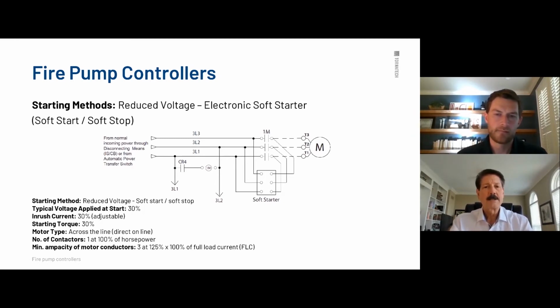So a soft start will allow you to do two things. You could ramp that speed up a little quicker if you want, or you could, it's field adjustable, but it's factory set for the optimum ramp up time for that particular horsepower size motor. You could ramp down and have a slow ramp down in cases of that too. I mean, you can go both ways. Really, you don't have to adjust that in the field, but once a soft start ramps up, it gets up to 100% motor speed. Now you're at optimum full load running amperage itself.